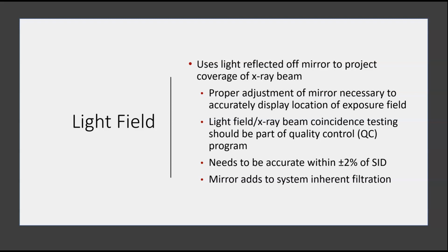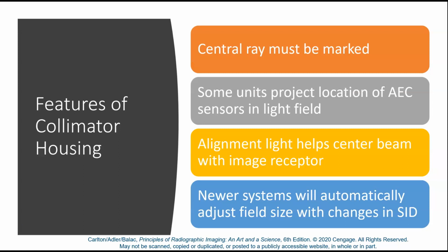So don't clip your fingers off or your toes or clip your knees or whatever because your light field, X-ray field is off. But please pay attention and just put those paper clips in the corners and make an exposure, and you'll be able to see which way it's off and how much it's off so you don't clip your fingers.